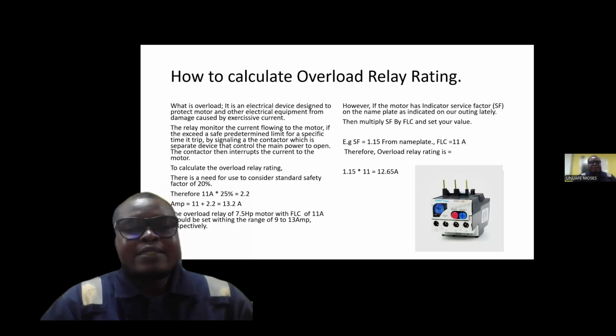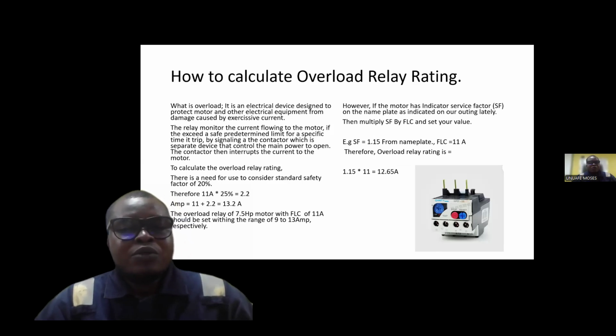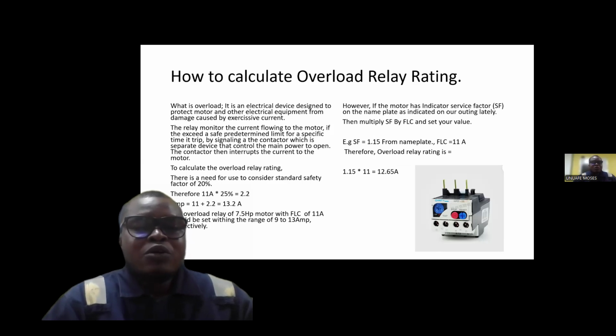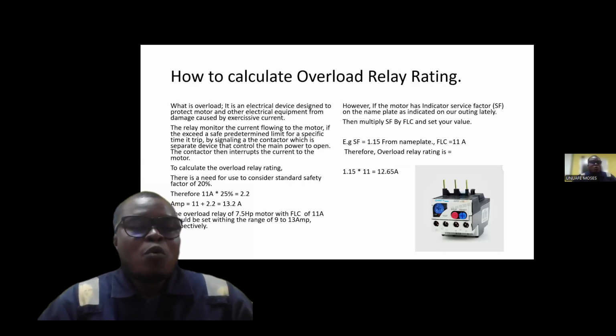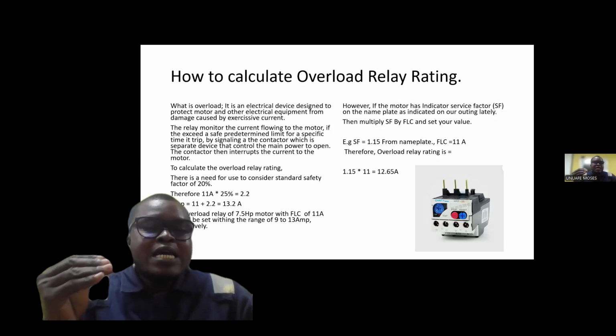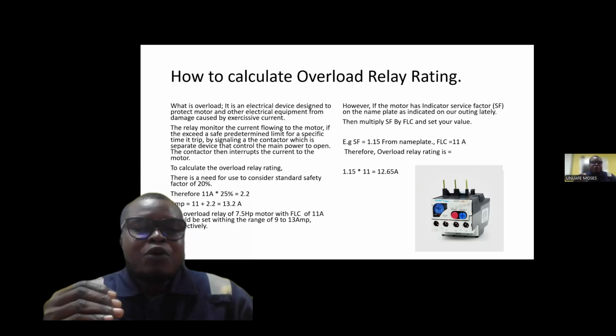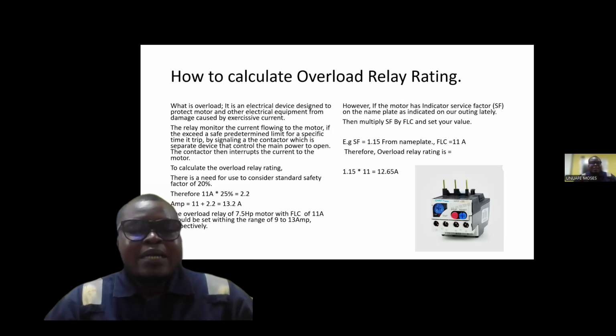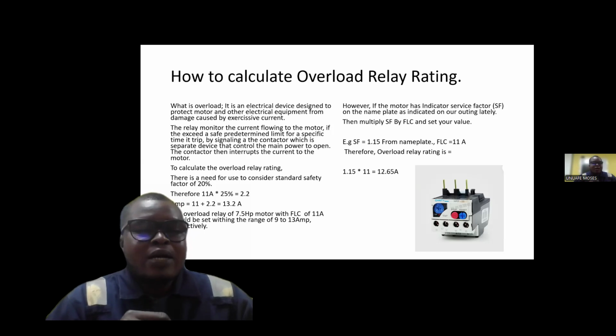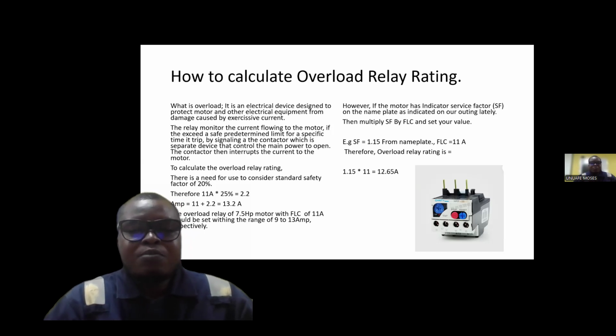We are not going to stop there. We also have to calculate the overload relay rating. But before we can calculate the overload relay rating, there is a need for us to know what the overload relay is. The overload relay is an electrical device designed to protect a motor and other electrical equipment from damage caused by excessive current. The relay monitors the current flowing to the motor. If it exceeds a safe predetermined limit for a specific time, it trips by sending a signal to the contactor, which is the device that controls the main power, to open, and then interrupts the current to the motor.